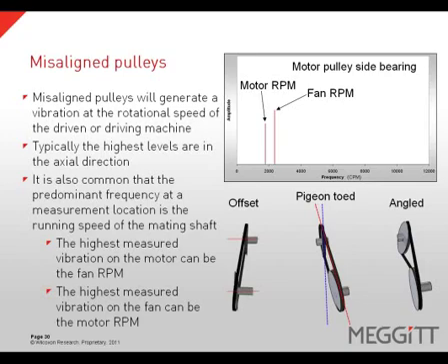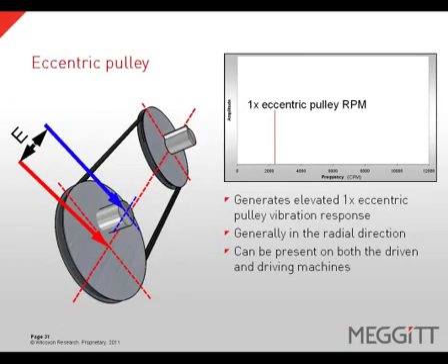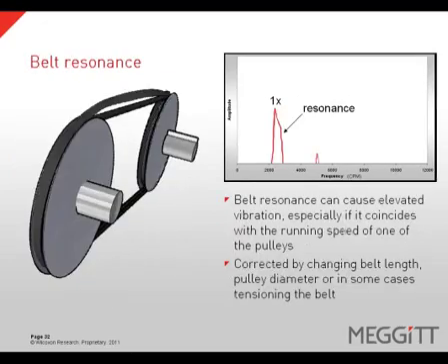An eccentric pulley will generate elevated levels of vibration at one-times the eccentric pulley's RPM. Generally, the vibration will be highest in the radial direction and can be present on both the driven and the driving machines. Belt resonance can cause elevated vibration, especially if it coincides with the running speed of one of the pulleys. This vibration can be corrected by changing the belt length, the pulley diameter, or in some cases tensioning the belt.